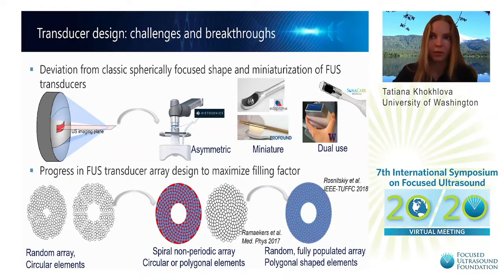As for transducer array design, the biggest progress there has been in the shape and arrangement of the array elements. In the past, random arrays with circular elements were used. And in order to maximize the filling factor of the array, recently spiral non-periodic arrays with circular or polygonal elements were proposed, and they helped with filling factor.